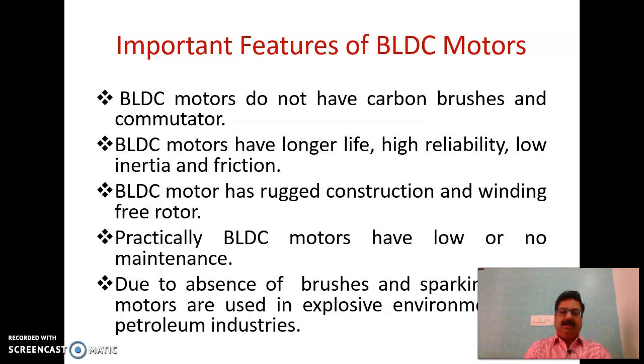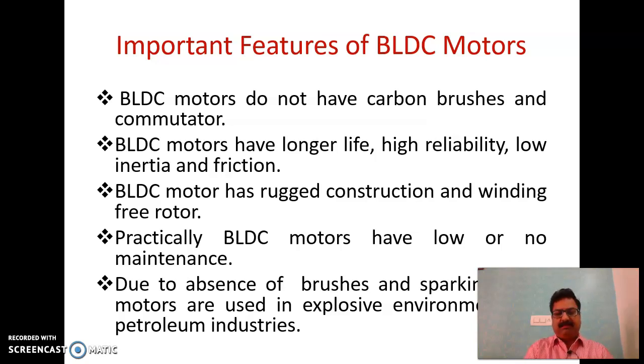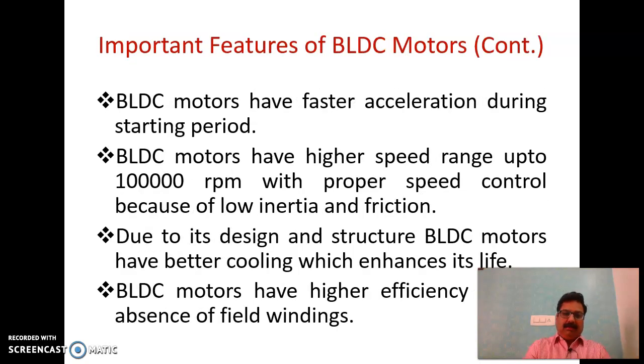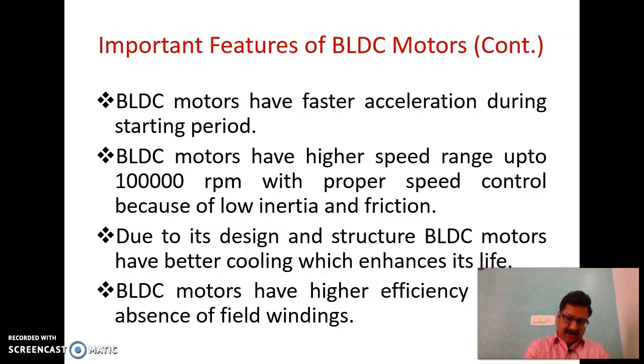Brushes are absent and sparking is also not present in the brushless DC motor. Therefore we can utilize them in places where an explosive environment is present — they have better application in explosive environments and the petroleum industry. Furthermore, because of low inertia, they have faster acceleration, and at the time of starting, faster acceleration is achieved.